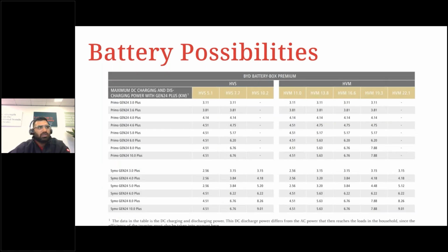All right, another little cheat sheet. With regards to different combinations, here we have different capabilities of charging and discharging with the batteries. The chart shows the DC charging and discharging rate of different inverter and battery combinations. An example scenario to consider is the charging and discharging possibility of a Fronius GEN24 Plus 10 kilowatt inverter with HVS 10.2 and HVM 11 battery. If you look at HVS 10.2, we can actually do 9 kilowatt charging and discharging, while HVM 11 can only do 4.51 kilowatt.